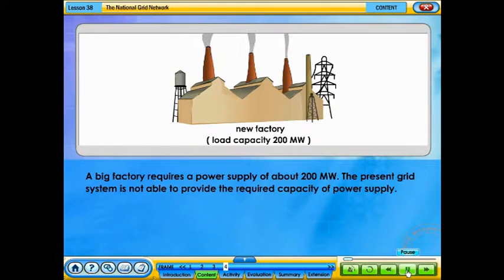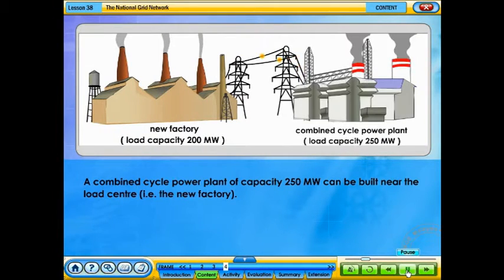A big factory requires a power supply of about 200 megawatts. The present grid system is not able to provide the required capacity of power supply. What would you do to solve this problem? A combined cycle power plant of capacity 250 megawatts can be built near the load center, that is the new factory.